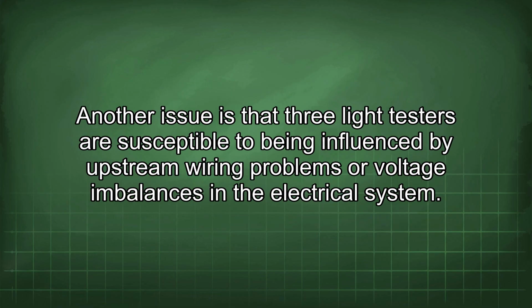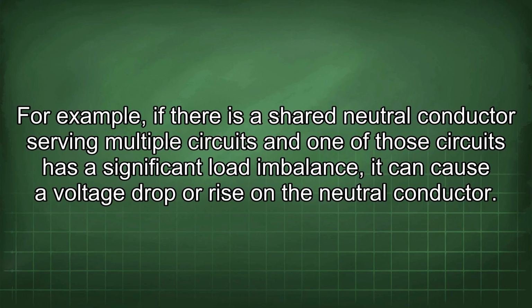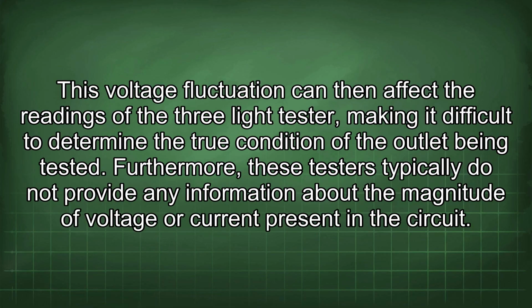Another issue is that 3-light testers are susceptible to being influenced by upstream wiring problems or voltage imbalances in the electrical system. For example, if there is a shared neutral conductor serving multiple circuits and one of those circuits has a significant load imbalance, it can cause a voltage drop or rise on the neutral conductor. This voltage fluctuation can then affect the readings of the 3-light tester, making it difficult to determine the true condition of the outlet being tested.